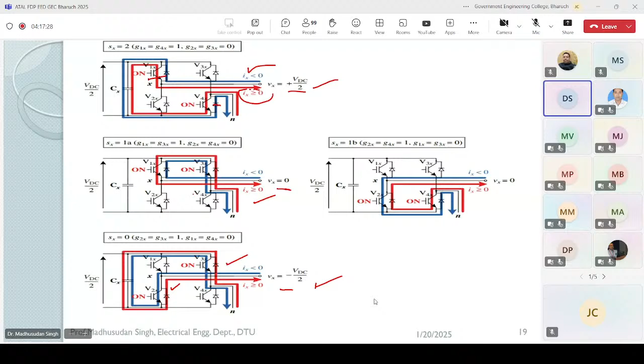So you see either plus VDC by 2 or minus VDC by 2 by operating 2 switches in pair, one from the upper side and the other from the lower side. Whereas for 0 voltage, you have to operate a pair of switches from the same side, either upper or lower. So this is the one configuration which is also used with some of the energy resources for converting these local energy into grid.